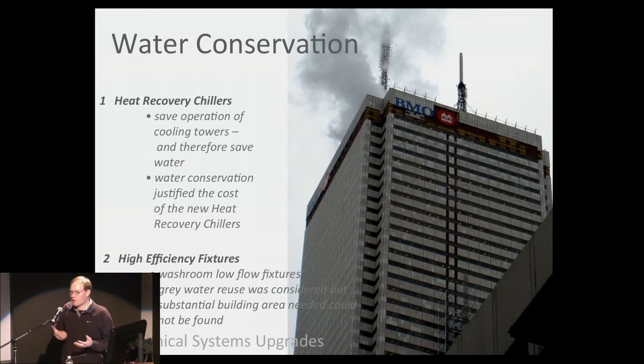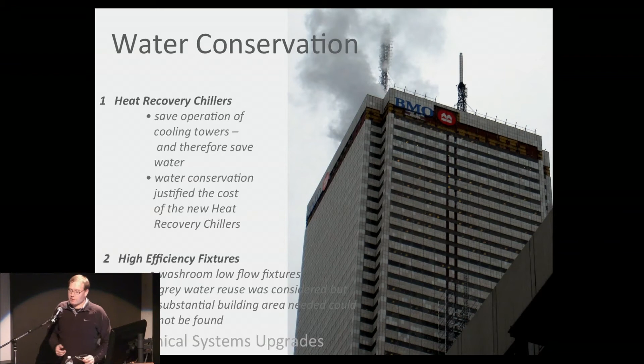Running those, saving the operation of those cooling towers — because we installed the heat recovery chillers, the savings in water evaporation for those cooling towers paid for all the new chillers in 3 years. That's how much water is pumped through this system. It's potable water, so you're charged a rate from the city. So the savings over 3 years from not running those cooling towers to the extent they were paid for, like $1 million worth of chillers. I found that pretty amazing — that's the kind of scale of the building.